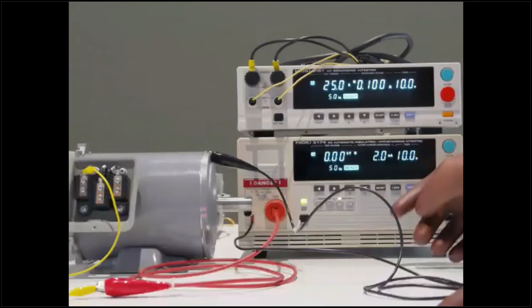This setting is already set for each mode, so I can just run the auto test. Firstly, as you can see, this is the withstand testing for 10 seconds. After that, this is the insulation testing, and it finishes OK, like this.